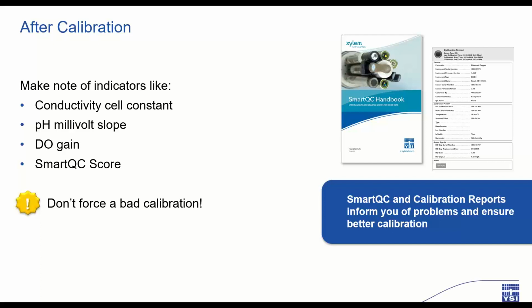After calibration, make note of indicators like the conductivity cell constant, pH millivolt slope, DO gain, and the QC score provided by the ProDSS and EXO software. These things will assist you in determining the success of your calibration. On a related note, you do not want to accept any calibrations that are out of range or giving warnings of questionable results. This indicates that there's a problem and further investigation is needed to determine the cause of the problem. Forcing a bad calibration is never a good idea, and it's likely that you will be collecting questionable data if you bypass all these warnings.